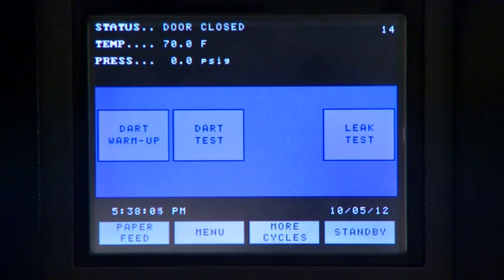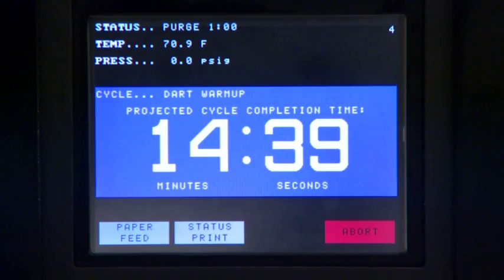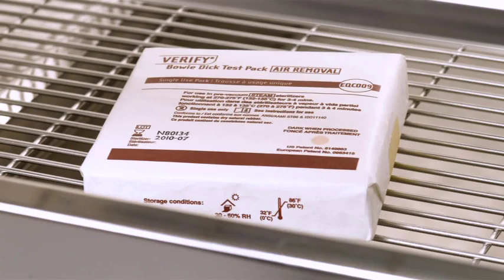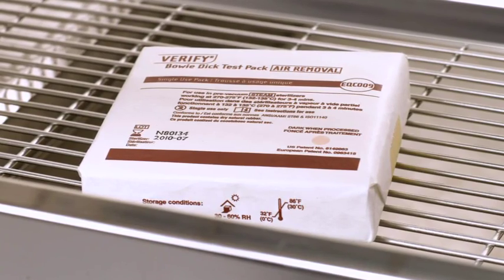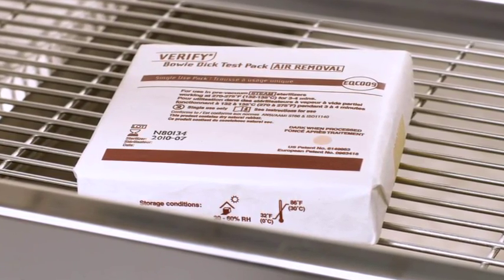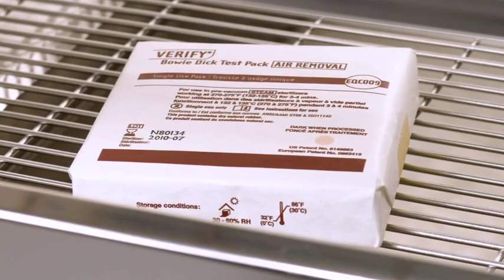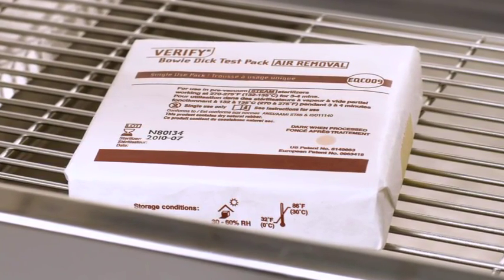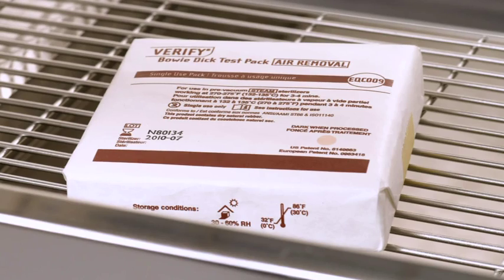To initiate a warm-up cycle, press more cycles until the test cycle screen appears. Press the warm-up cycle button. Once the warm-up cycle is finished, place a DART test or properly prepared Bowie-Dick test pack or commercially available test pack on the lowest rack of the sterilizer loading cart and load the cart into the chamber as usual. Place the challenge pack flat, not on edge, on the bottom shelf close to the door above the chamber drain, or as near as is practically possible.